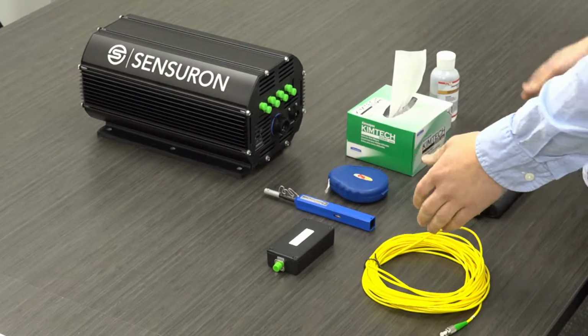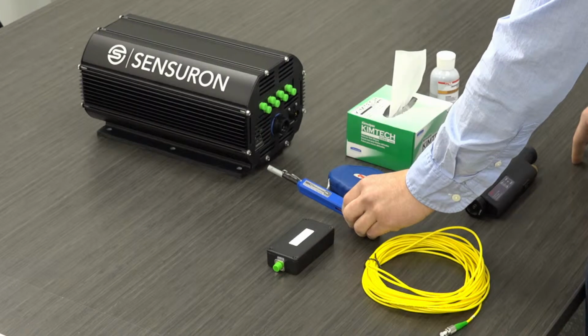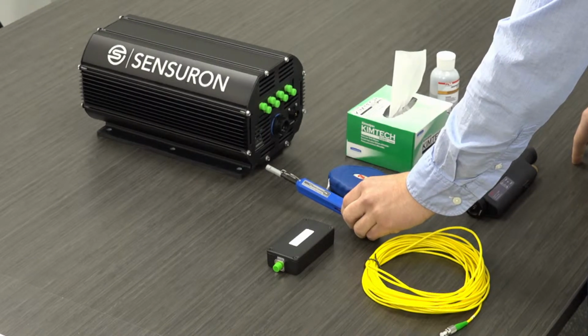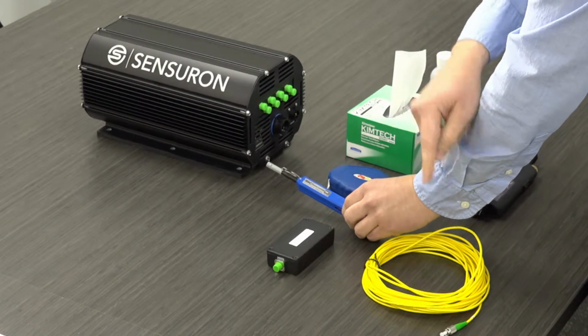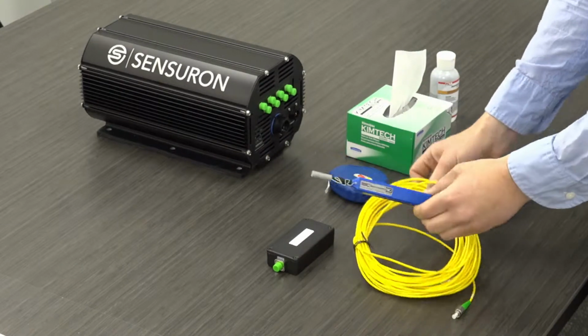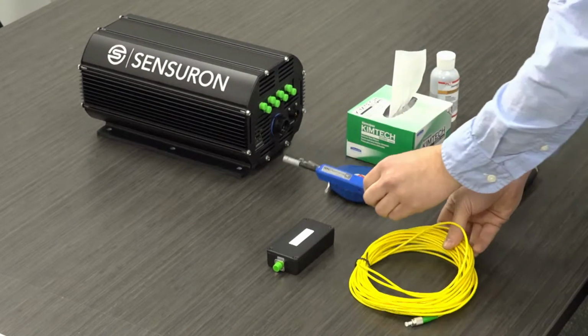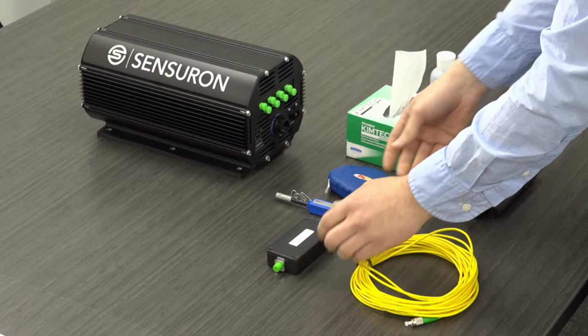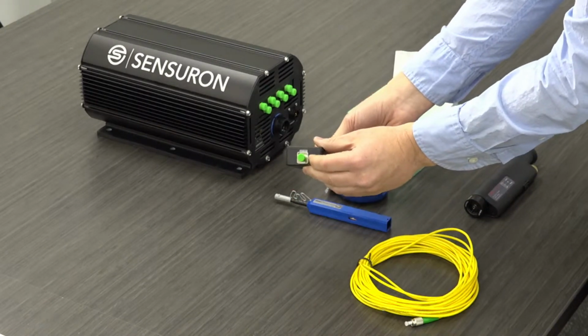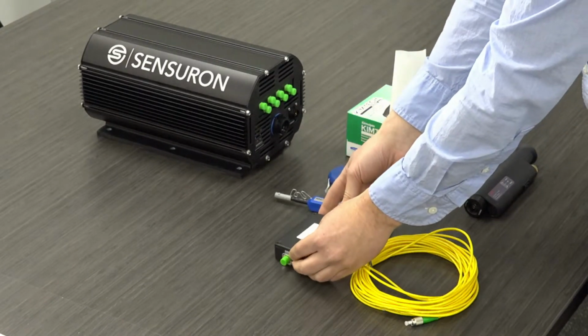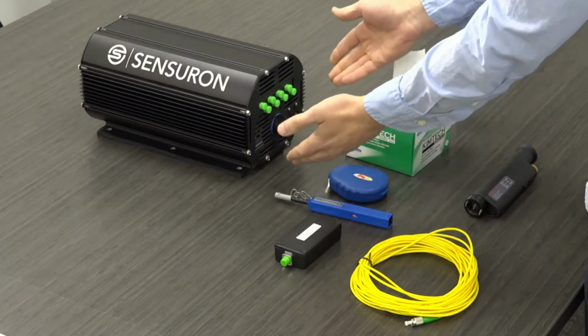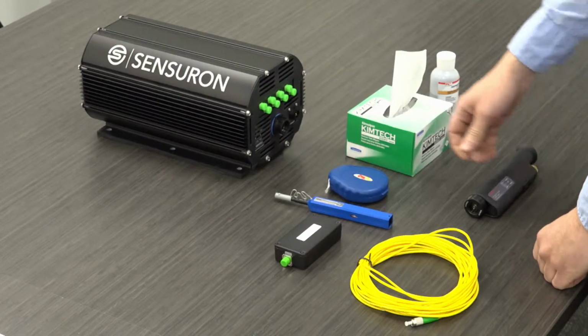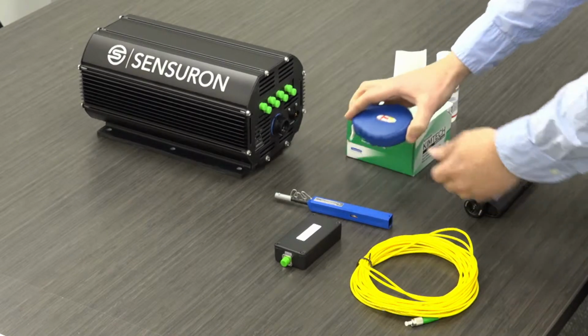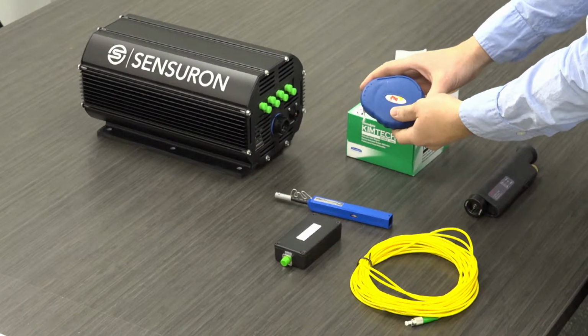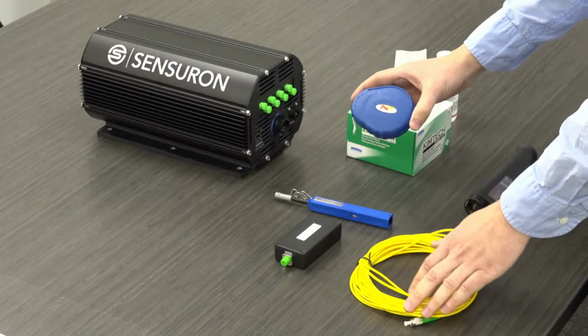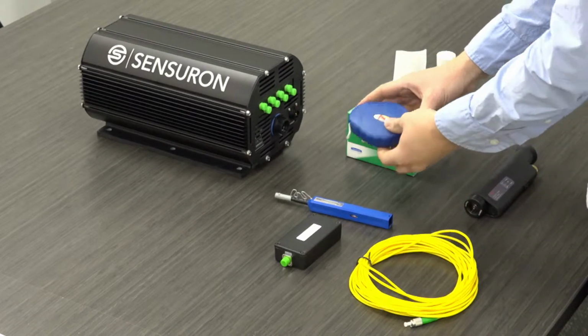On the cleaning devices side, we have right here what we call a click connector. This is a device which can be used for both cleaning the exposed connectors, such as on this FC-APC patch cord, and it can also be used to clean the internal connectors on the inside of these FC-APC mating couplers. You see those on the broadband reflector and on the front panel here of the system. Just to the right of that, we have this ferrule cleaner. So this device is only used for cleaning the exposed connectors, such as on the lead cables.